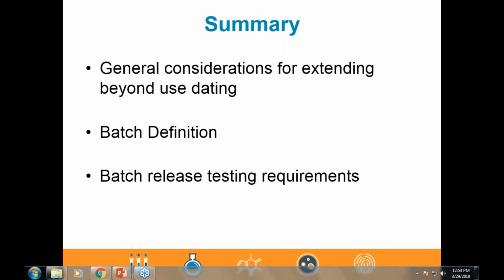Linda, we have another question. What if you're making a batch for a single patient and it is a month's supply? Do you need to do a method suitability test and submit 4 vials for testing? Method suitability is appropriate for any number. If you're conducting a sterility test, you need to have shown that the method is suitable for which you're conducting. So whether you're doing 1 test or 100, a sterility test should have a method suitability, which is like a validation of that particular sterility test before even running the test. It's part of the test itself.